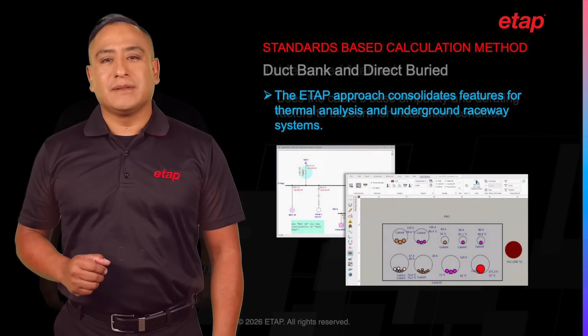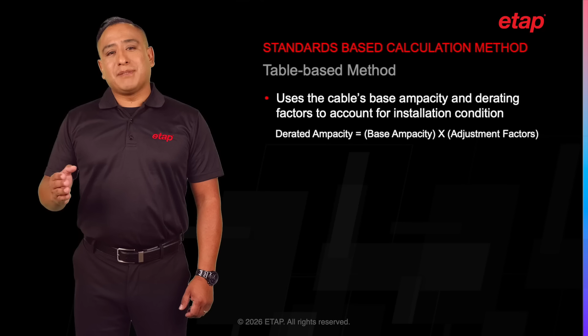The standard-based method is also referred to as table-based method because it uses the cable's base ampacity and derating factors to account for the actual installation condition. Base ampacity tables and correction factors are provided by the standard, typically in a table-based format. To determine the derated ampacity of the cable, the base ampacity is multiplied by all applicable adjustment factors.